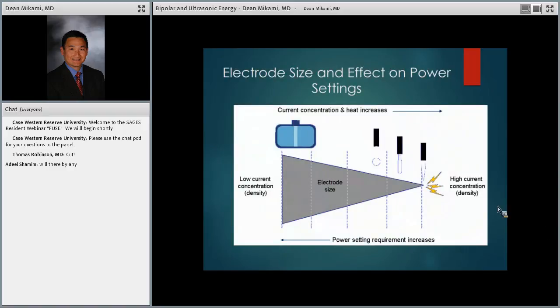Okay, so just like I said here, in the blue, you have your dispersive electrode. For all your residents out there, when you go to the OR tomorrow, the nurse is going to ask you, where should we put the grounding pad? And you say, wait a minute, it's not a grounding pad, it's our dispersive electrode. Our ESU wants to complete the circuit, so where should you put your electrode? Your dispersive electrode should be as close to your operative site as possible. So if you're doing a right inguinal hernia, you probably should put that dispersive electrode on the right thigh, right? You want to find a nice flat surface. If there's hair on that, that's going to affect the current going to the dispersive electrode, so you want to shave that hair. If somebody has an implant, you want to stay away from metal, because the metal will conduct the current.